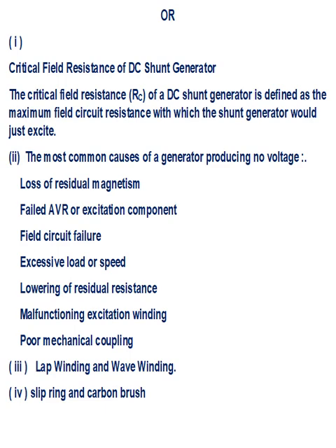Part 2 answers. Loss of residual magnetism, failed AVR or excitation component, field circuit failure, excessive load or speed, lowering of residual resistance, malfunctioning excitation winding, poor mechanical coupling. Part 3 answers. Lap winding and wave winding. Part 4 answers. Slip ring and carbon brush.